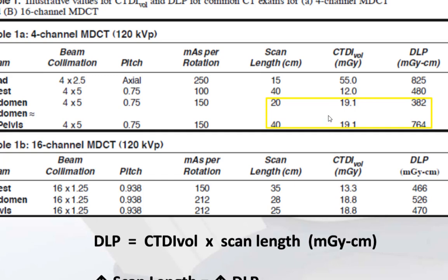Scan length will change the DLP but will not change the CTDI. For example, a CT abdomen has a shorter scan length than CT abdomen and pelvis. CTDI volume remains the same — say 19.1 mGy — but the DLP will double because we have doubled the scan length. So DLP equals CTDI volume times scan length, and increasing scan length will increase DLP and therefore increase the effective dose.